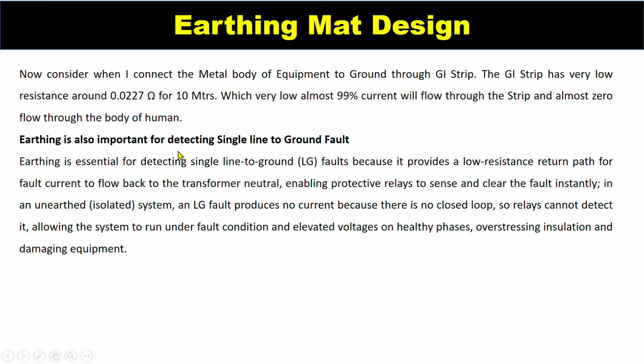Earthing is also important for detecting single line to ground faults. This point, that is earthing, is used for detecting single line to ground faults. I will show you on the ETAP. Earthing is essential for detecting single line to ground faults because it provides a low resistance return path for fault currents. Fault current flows back to the transformer neutral, enabling protective relays to sense and clear the fault instantly.